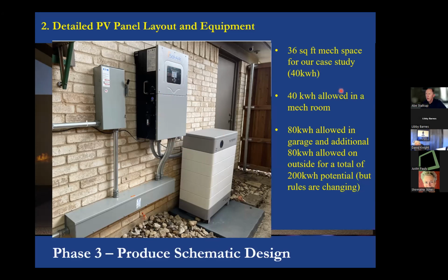A few more rules of thumb: 36 square feet of space for our case study's 40 kilowatt hours. You're only allowed 40 kilowatt hours in a mechanical space or storage room inside the house - this is important due to fire code issues. Garages will allow 80 kilowatt hours, plus an additional 80 to 120 outside, for a total of 200 kilowatt hours on site. Those rules are changing in July of 2024 - I believe it's tripling - though for most homes you're never going to need more than 200 kilowatt hours, but for what it's worth.